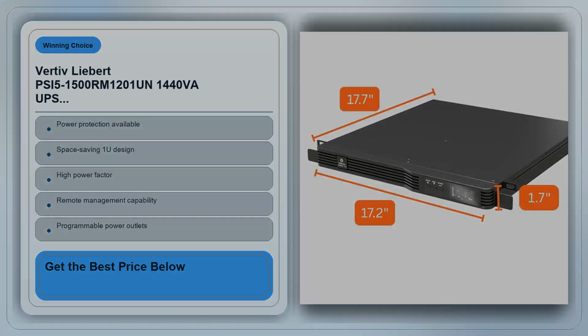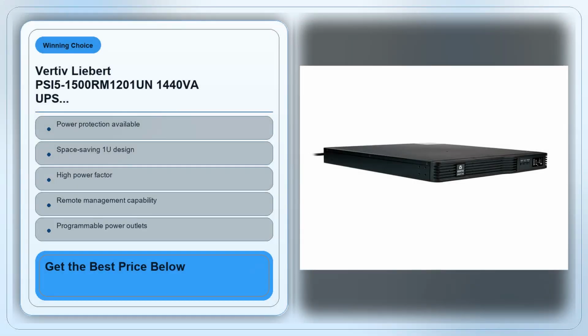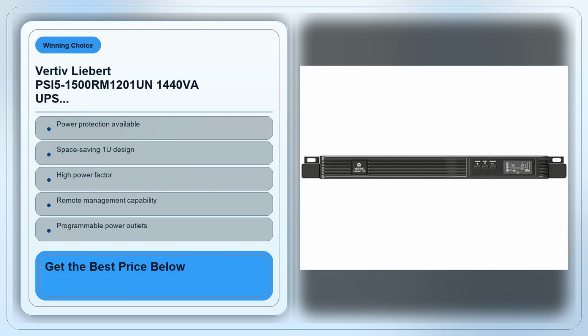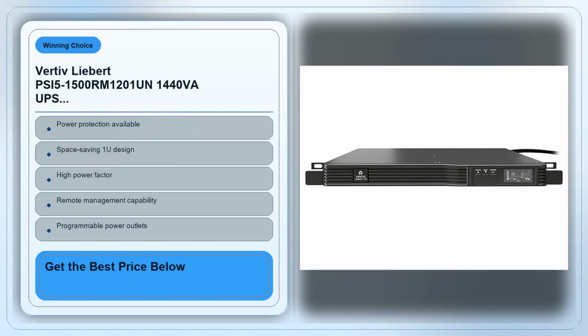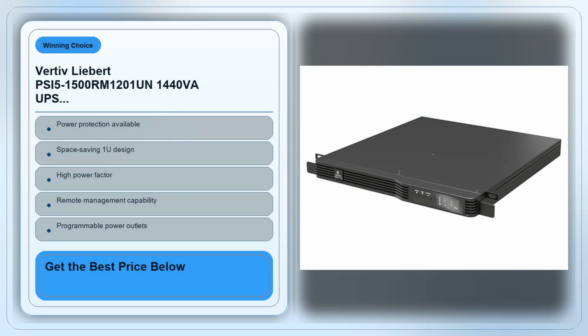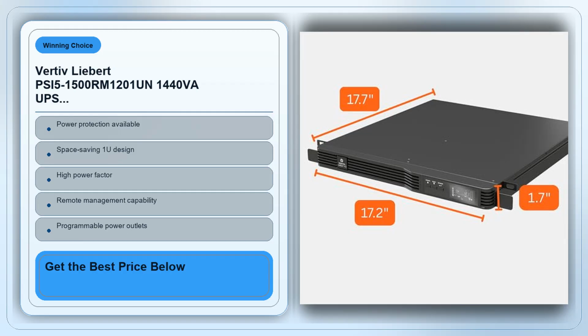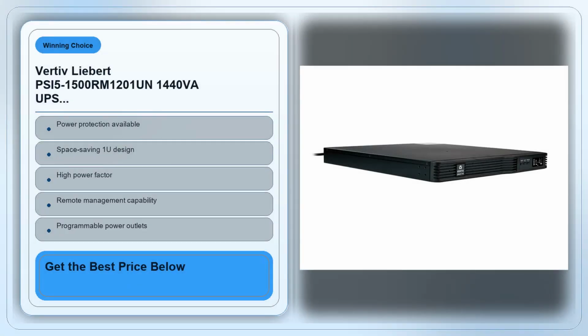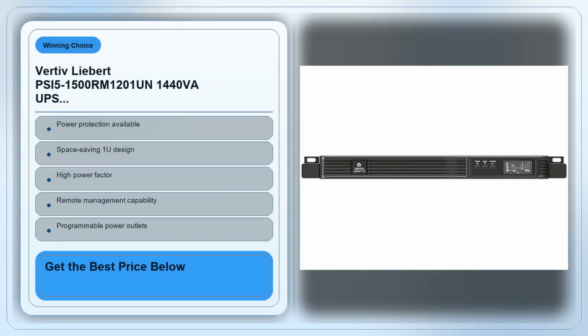Now, let's get into the day-to-day reality of setting this up. Because it's a 1U unit, you'll need to make sure the rack's rear panel has enough clearance for the airflow. The unit pulls cool air from the front and exhausts out the back, so you can't just jam it against a wall of other equipment without a bit of breathing room. In my own test rig, I left at least an inch of space between the UPS and the adjacent switch, and the temperature stayed well below the 40°C threshold that manufacturers warn about. That's a practical tip. Plan a little extra clearance when you design your rack layout, otherwise you might find the UPS throttling its output just because it's overheating.